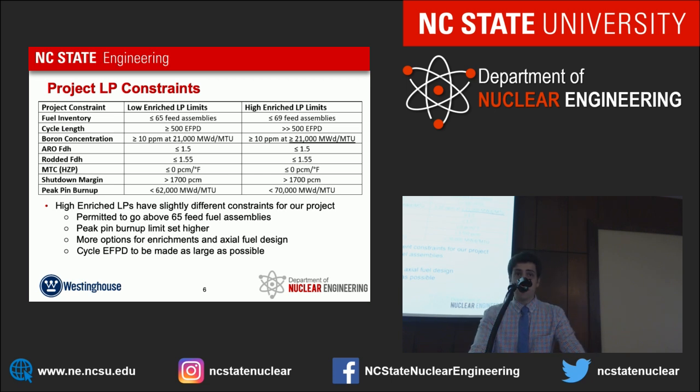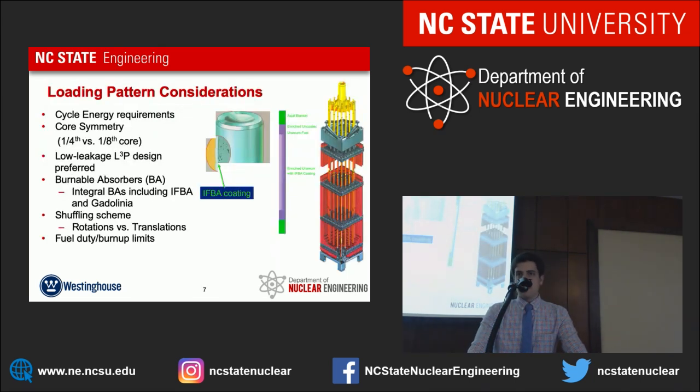And so for the moderator temperature coefficient, it has to be negative throughout the cycle, starting at hot zero power. If it's negative at hot zero power, then it should be negative in all cases. And the shutdown margin above 1700 PCM reactivity, and burnup cannot exceed 62,000 megawatt days per MTU for the low enriched. And for the high enriched, of course, we can take that burnup limit higher, to 70,000.